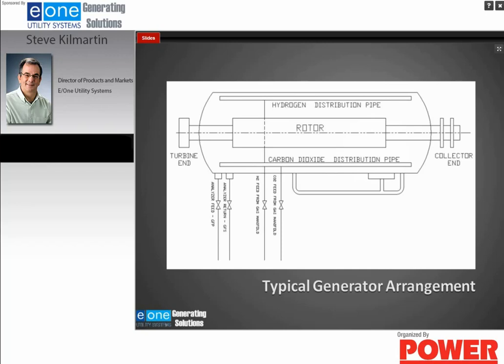So this generator is filled with air, and I want to get that air out of there. So what I'm doing is I'm connecting my CO2 supply to my CO2 feed line, and I'm going to be pushing carbon dioxide in the bottom distribution pipe. Because carbon dioxide is heavier than air, it will create a blanket, and as I put carbon dioxide in the generator, it's going to force air out the hydrogen distribution pipe on the top. So I want my analyzer located on the hydrogen feed line that's coming from the hydrogen distribution pipe. So as I fill that generator with carbon dioxide, the air is coming out of the hydrogen distribution pipe, exiting to the vent.